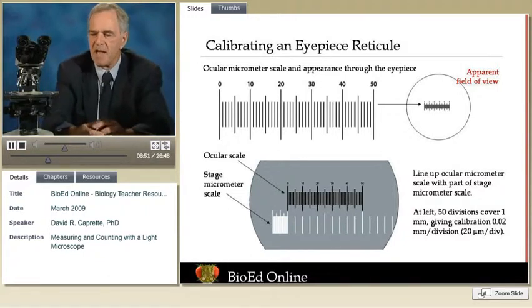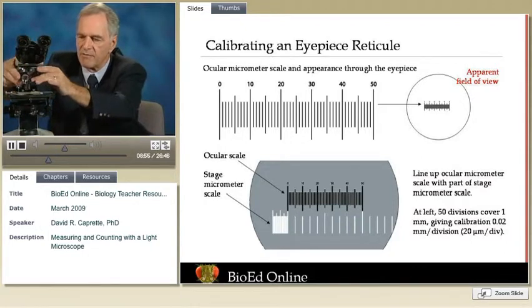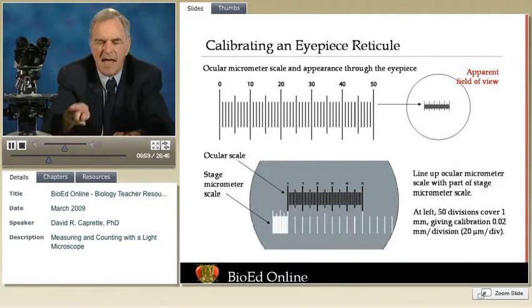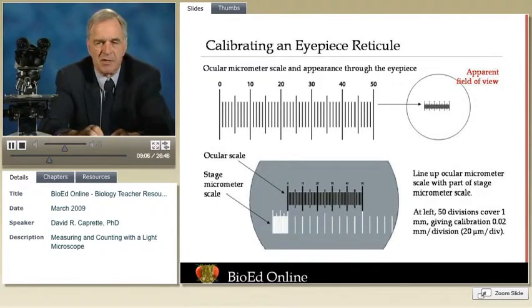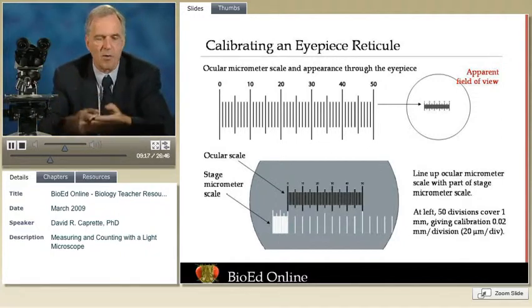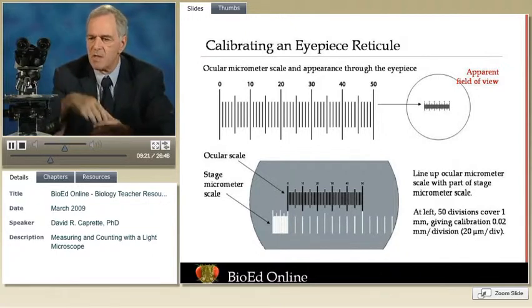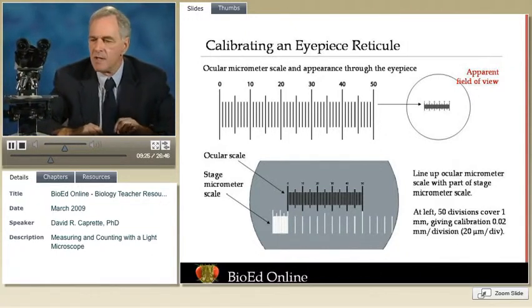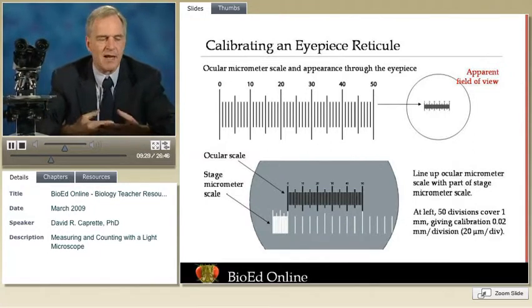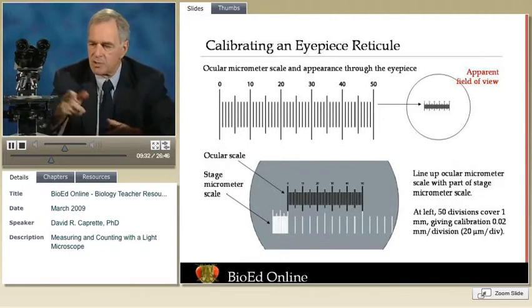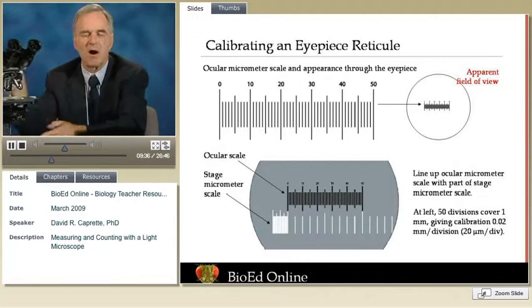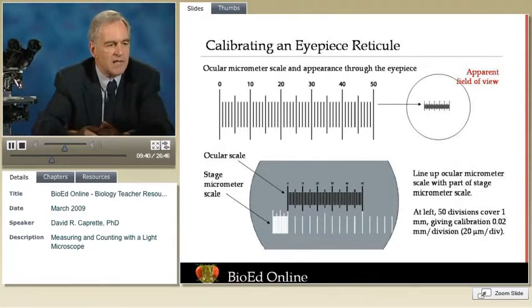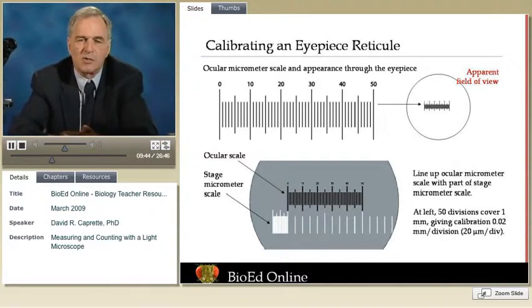Now, if we change magnifications, let's say we go from 40 power all the way up to 400 power, then the calibration changes in inverse proportion. So if we had 20 micrometers per division at 40 power, we're going to have 2 micrometers per division at 400 power. And likewise, if we were to go to 100 power or to 1,000 power, again, the calibration changes proportionally. Once you're calibrated at any particular magnification, you can just do the division or multiplication to get the calibration at any other magnification, even if you use a new objective lens, as long as you know the magnification of the lens itself. So we have our ocular micrometer here at 40 power that's lined up so that each division is 20 micrometers wide.